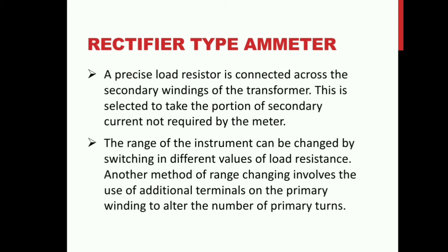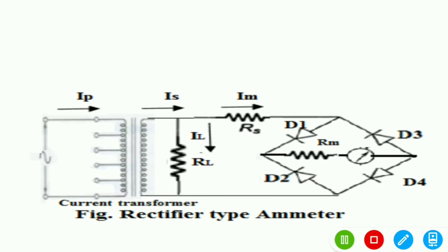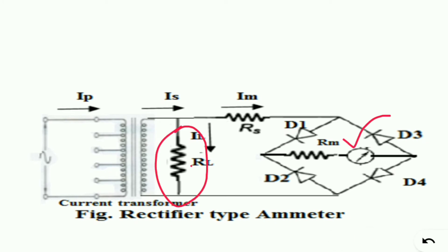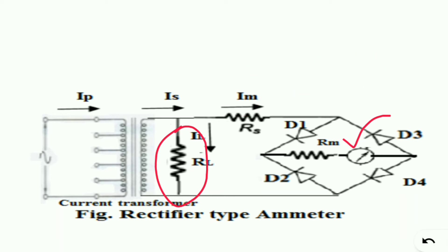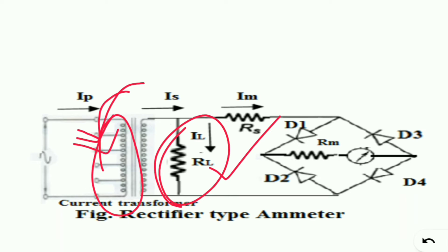The range of the instrument can be changed by switching in different values of load resistance. Another method of range changing involves the use of additional terminals on the primary windings to alter the number of primary turns. So we have two methods: we can change the resistance, or we can change the primary windings.